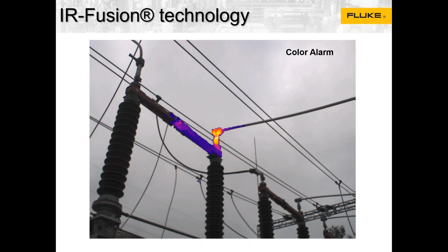The lens selection is also very important. If you are measuring, for example, in a confined space, you can use a wide angle lens to have a wider angle and more details. If you want to measure a far distance, you can use 2x or 4x lenses. And if you are working on electronic parts, for example a printed circuit board, you can use the 25 micron lens here. So using lenses is very important.